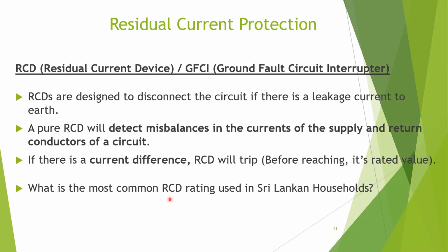But when it comes to RCDs, they are a little bit different. Usually there's a rating of the RCD. It is the must-trip value, so it should trip before the rating. Let's say your RCD is rated for 100 milliamperes. It should never go to more than 100 milliamperes before tripping. It should trip before 100 milliamperes. Usually we say RCDs will trip between half of the rating and its rating. So a 100 milliampere RCD will trip if the leakage current is higher than 50 milliamperes or less than 100 milliamperes. That is the principle of the rating of these RCDs.